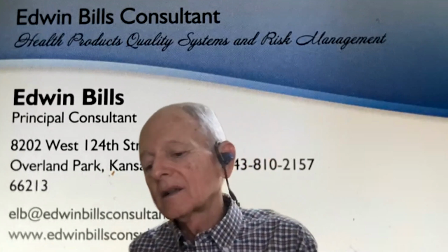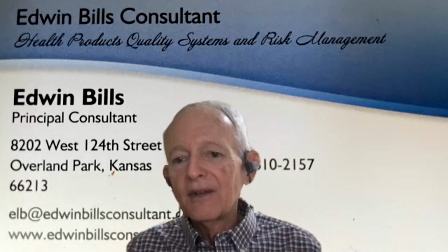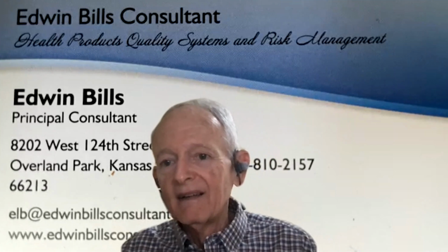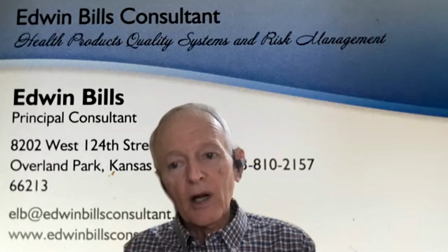It does. But the other thing I wanted to bring up is that my product does this, but there's another product on the market that is similar, and I have to compare my product to that other product to see if I'm at least equivalent to it or better. Then I can put the product on the market. If my benefit risk is less than the other product, then I've got some work to do. And the other product could be a medical device, a drug, or a biologic. Yes. It's not limited to just device.